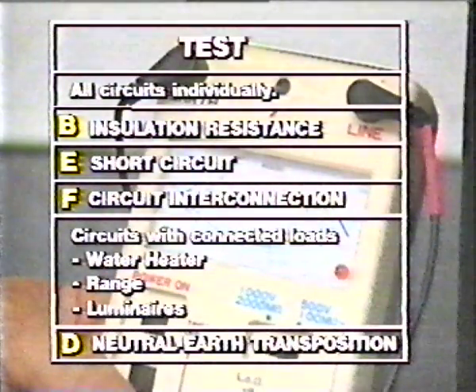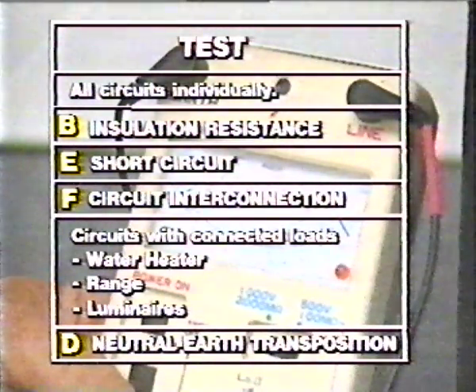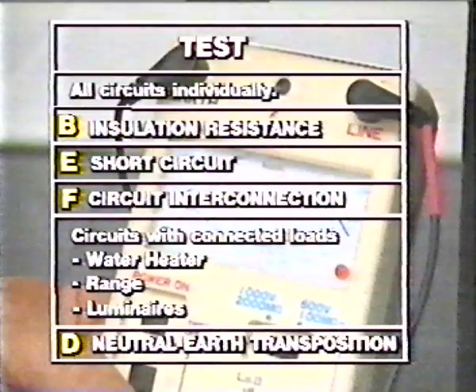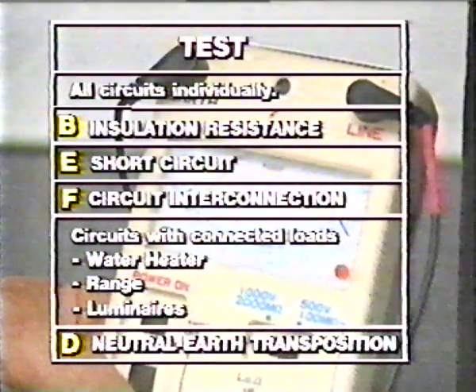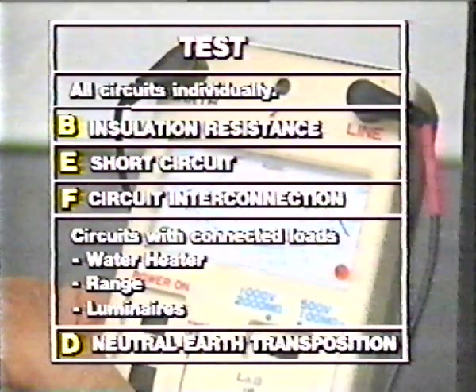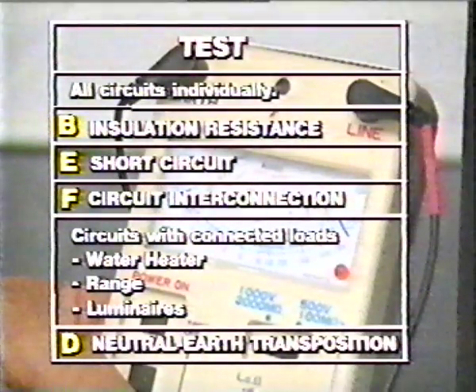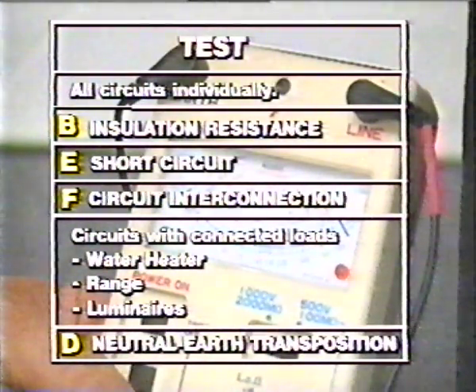Circuit interconnection is now tested as in test F, using an ohm meter to test between the neutral conductor of each circuit and all other neutral conductors, and between the active conductor of each circuit and all other active conductors on the same phase.